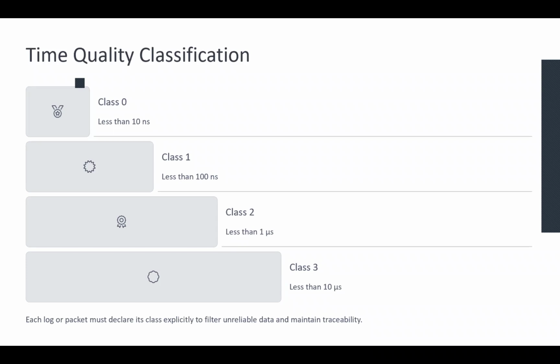Okay, not all subsystems can maintain perfect synchronization at all times. You have to note that. So it's critical for each data point, control action, or measurement to carry a quantifiable statement of how confident it is about the timing. So IEEE C37.118 basically mandates metadata tagging, where every time-tagged event must explicitly declare the quality of the synchronization.